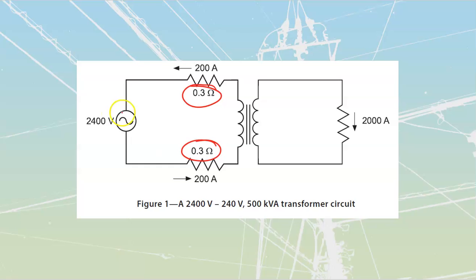If I take a look at this, on my primary side I've got 2400 volts, but 0.3 of an ohm, which is relatively small resistance. However, if I'm passing 200 amps through there, I'm going to end up with a voltage drop. 0.3 of an ohm multiplied by 200 amps is going to tell me the voltage drop that I would have here.